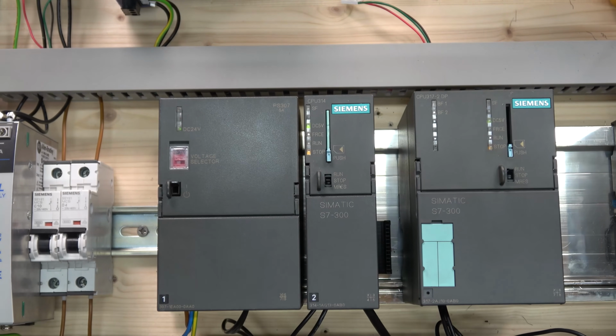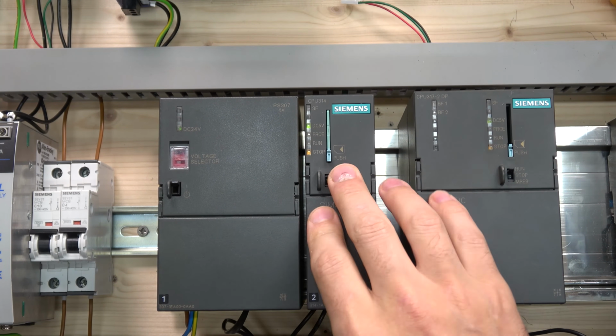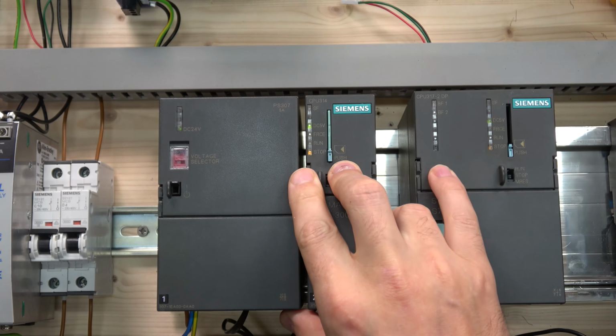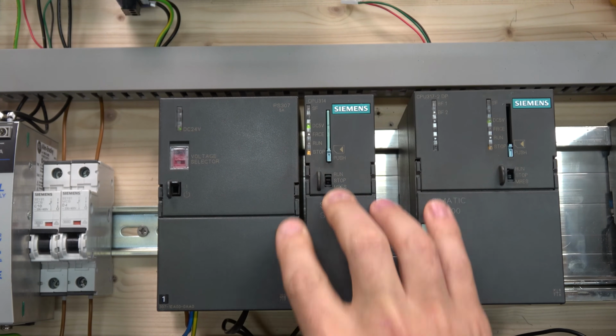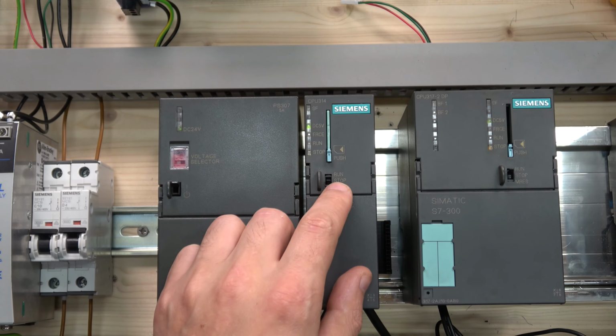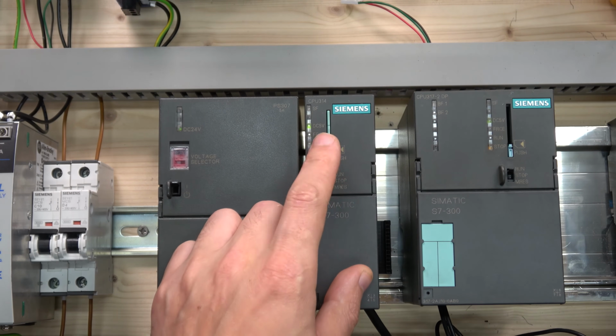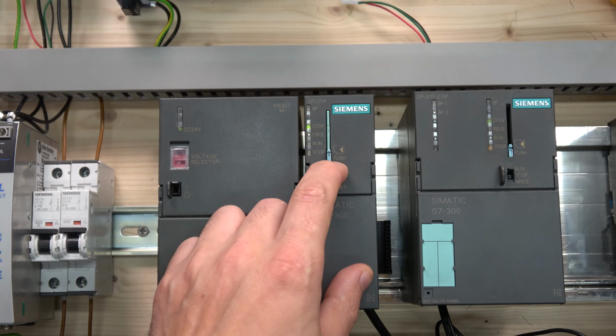Here we are. So there's a PLC. As you can see, I've been busy, playing a lot with the different things, especially with the Simatic Net today. As you can see, my CPU in here is flashing stop, and even if you reset it, it's trying to do something but doing nothing, so it's going back into stop. You put it into run, nothing's going to happen, and SF is not going to come up either.